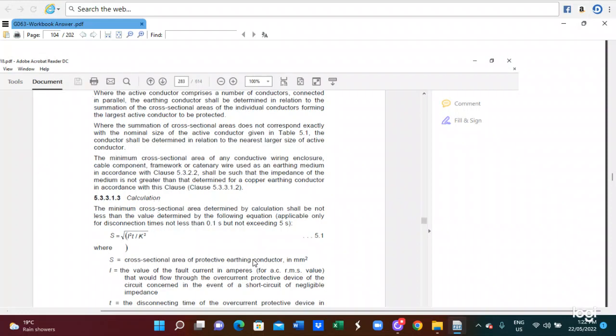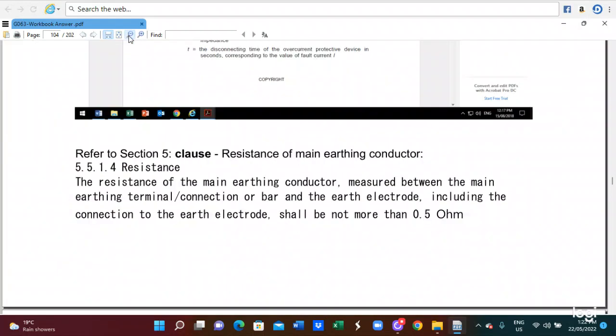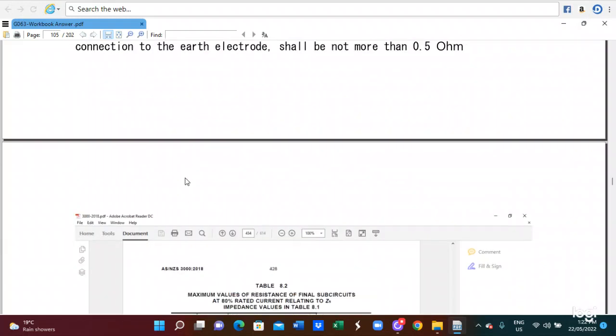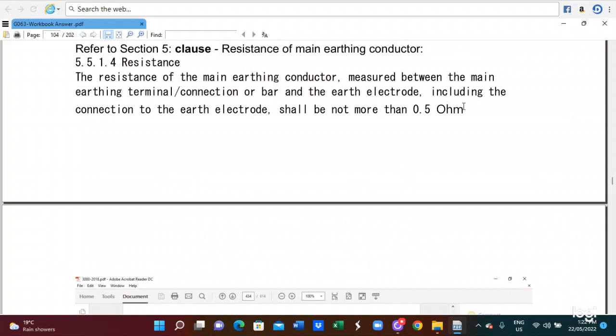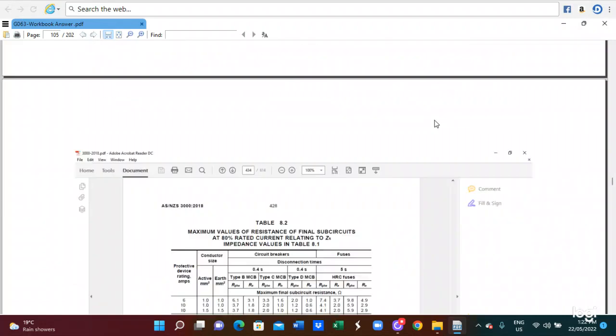3.1.3 is a calculation method. Cross-sectional area is a calculation. And also section 5.5.1.4 covers the resistance of the main earthing conductor. You can read it from here. The resistance of the main earthing conductor is not more than 0.5 Ohm.